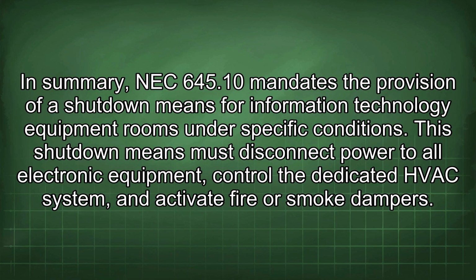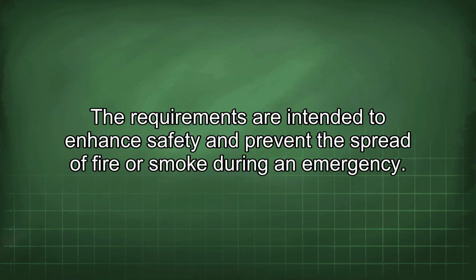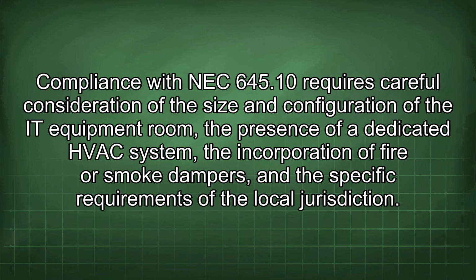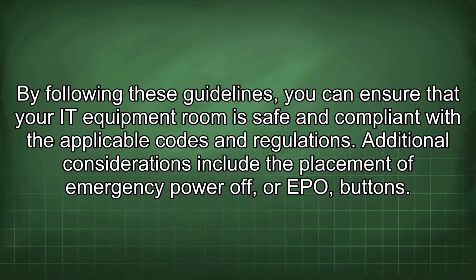This shutdown means must disconnect power to all electronic equipment, control the dedicated HVAC system, and activate fire or smoke dampers. The requirements are intended to enhance safety and prevent the spread of fire or smoke during an emergency. Compliance with NEC 645.10 requires careful consideration of the size and configuration of the IT equipment room, the presence of a dedicated HVAC system, the incorporation of fire or smoke dampers, and the specific requirements of the local jurisdiction.